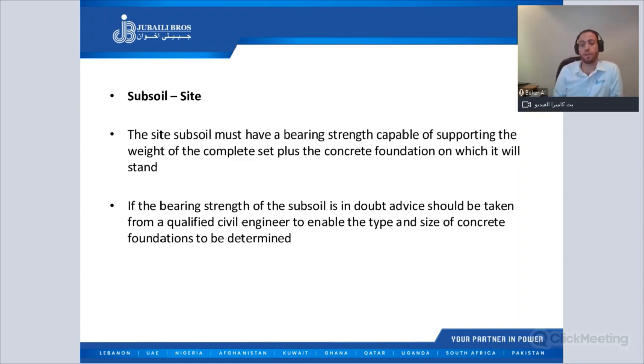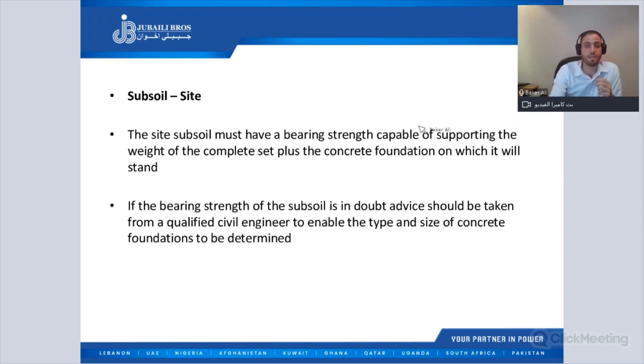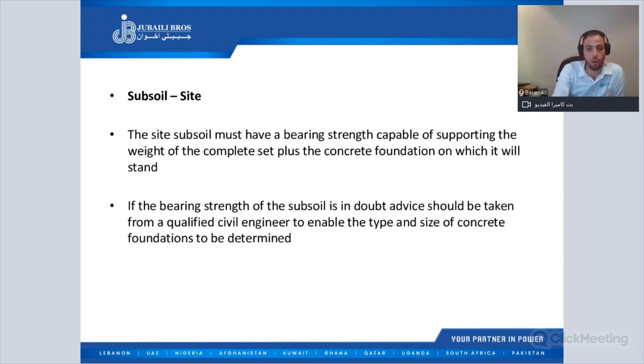Before installing the generator inside the room and before making the foundation, the most important point is to check the subsoil at the site. The subsoil must have a bearing strength capable of supporting the weight of the complete unit plus the concrete foundation on which it will stand. If there is any doubt about the soil, advice should be taken from a qualified civil engineer to enable the type and size of the concrete foundation to be determined.